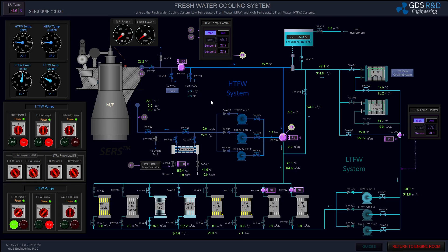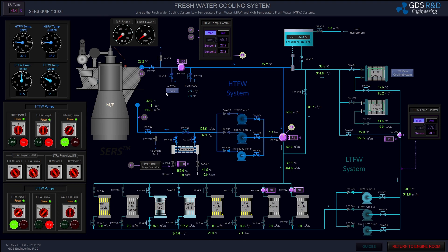I'm opening the inlet valves of the high temperature fresh water pumps and the preheater bypass valve. Instead of the bypass, I will switch the fresh water flow to the main engine preheater. I will close the bypass valve and start the preheating pump and start fresh water circulating.